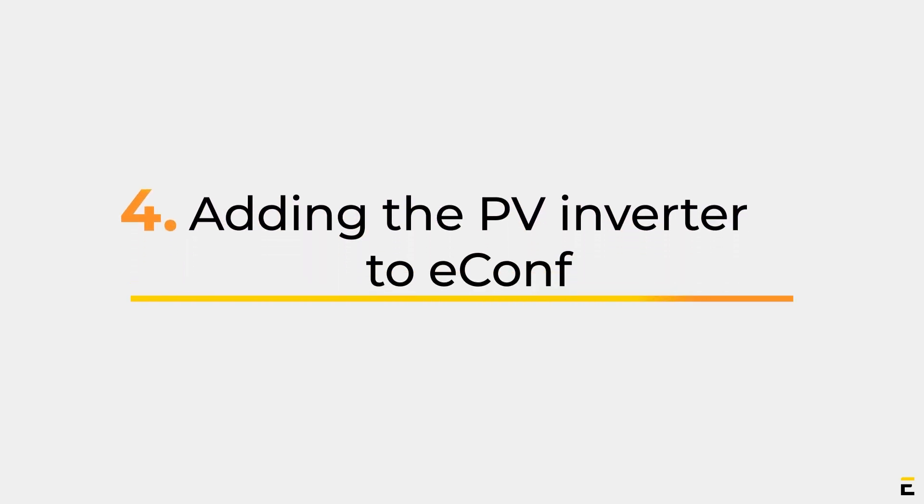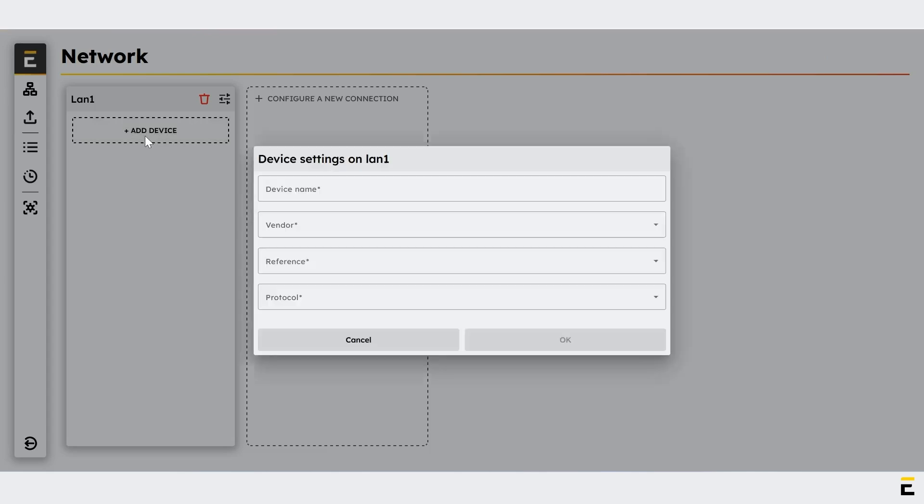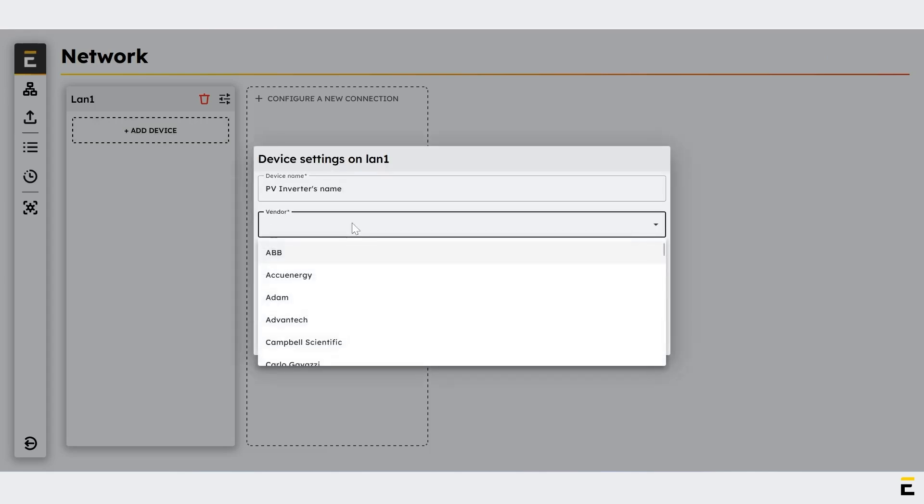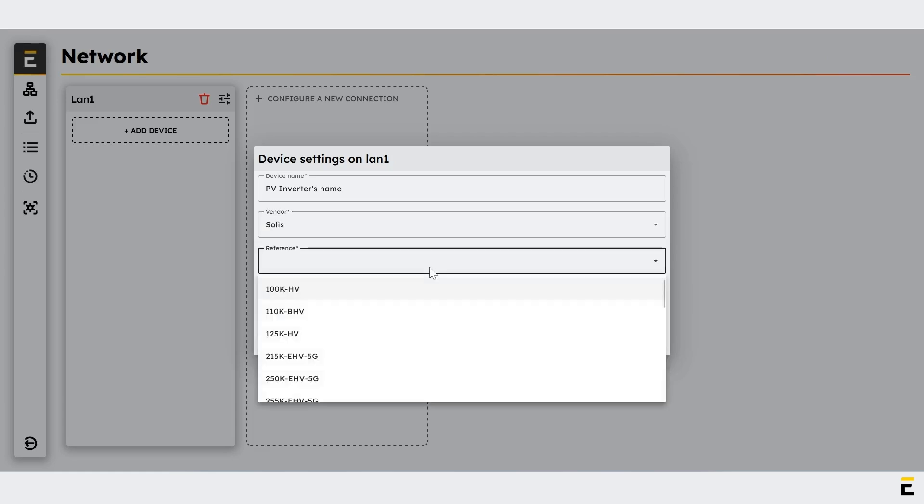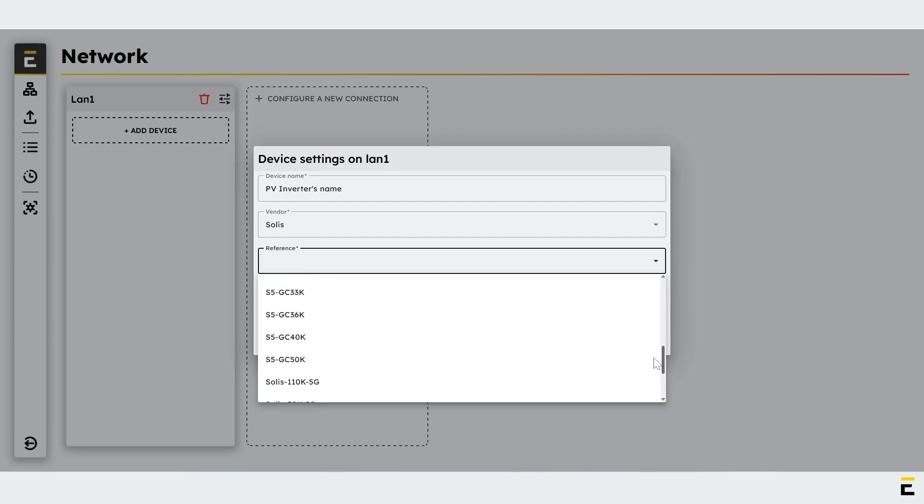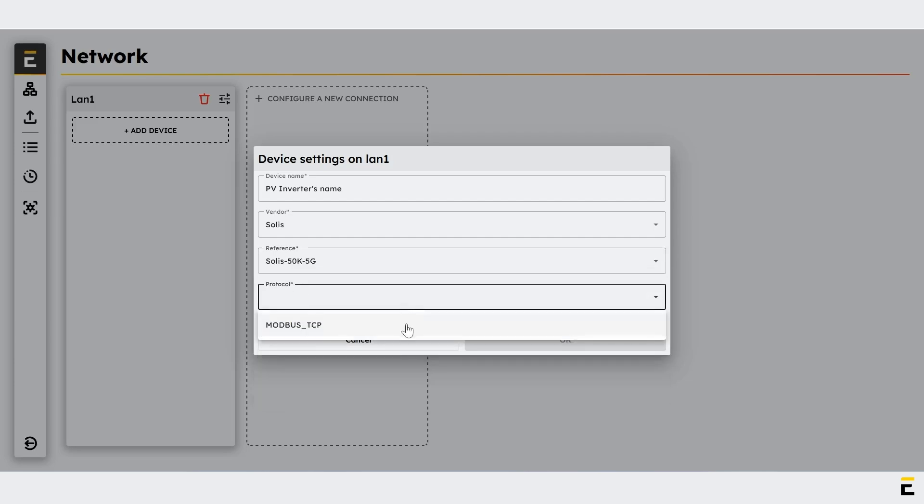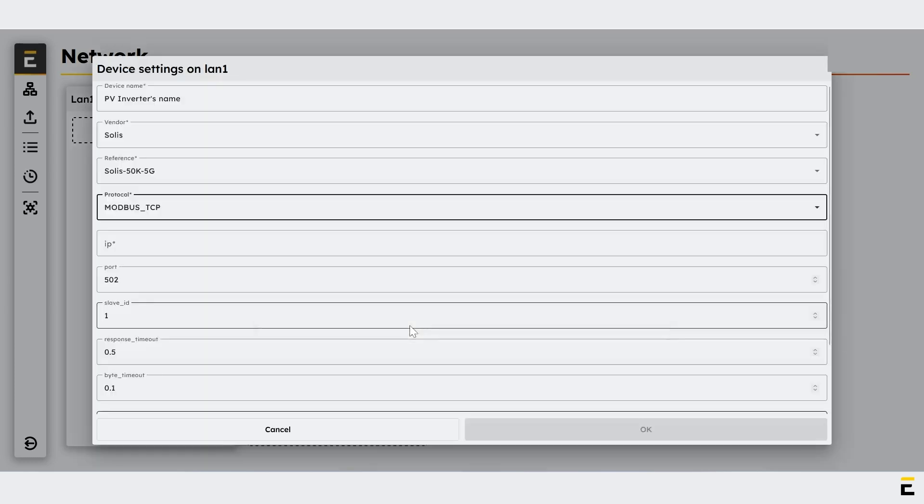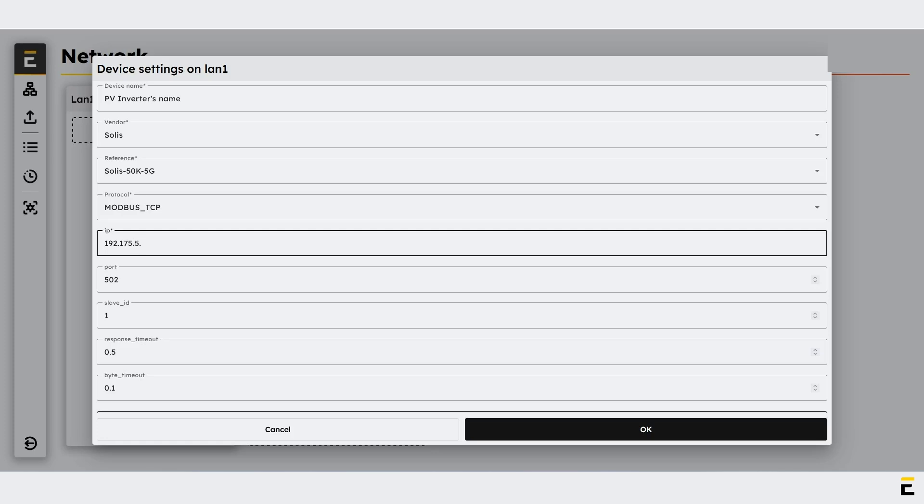Part 4: Adding the PV Inverter to e-conf. In the column specific to the LAN 1 connection, click on Add Device. Enter the device name. Select the PV Inverter's vendor from the drop-down list. Select the reference of the PV Inverter from the vendor-specific drop-down list. Select the Modbus TCP protocol for communication between Ellum's device and the PV Inverter. Enter the IP address of the PV Inverter.